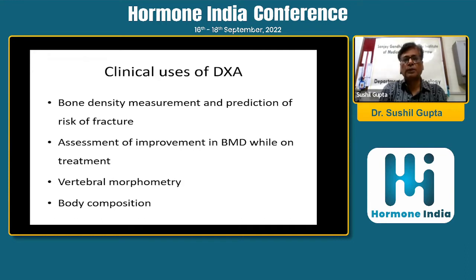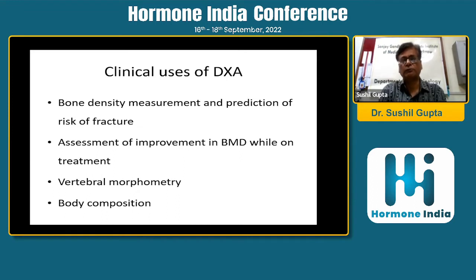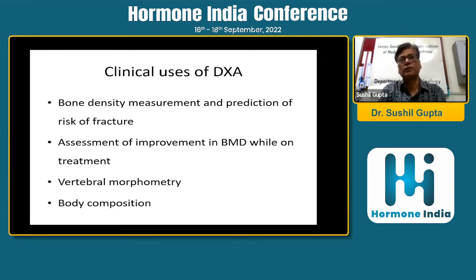We use DEXA for measurement of bone mineral density because BMD is a predictor of the risk of future fractures. Once we start treatment, it is extremely important to assess how much BMD is improving, deteriorating, or remaining stable over time. In addition, newer modalities have arrived, like vertebral morphometry where we measure vertebral heights to detect spinal fractures, and body composition analysis to measure fat mass, lean mass, android-gynoid ratio, and other parameters influencing BMD and overall body function.